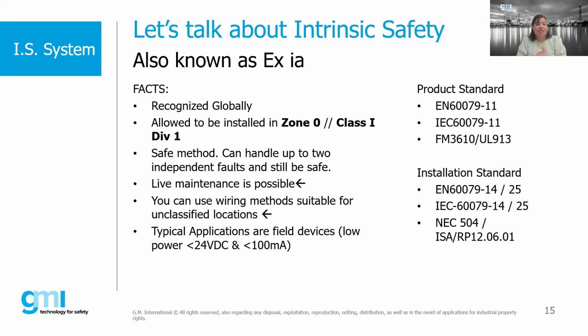We have put here also the standards that are relevant when you're working with intrinsic safety. So -11 will be for manufacturers when you are designing an intrinsically safe device for ATEX, IECEx. And then you have the FM and UL standards for North America for designing the product itself. For installation, which I think is the majority of you listening to this event, when you are purchasing intrinsically safe items and you're going to install them, then you need to follow the installation standards, -14 and -25 for ATEX, IECEx. And for North America, we have the NEC, the National Electrical Code, Article 504, which only talks about intrinsic safety, and the RP 12.06 about installations of intrinsic safety.